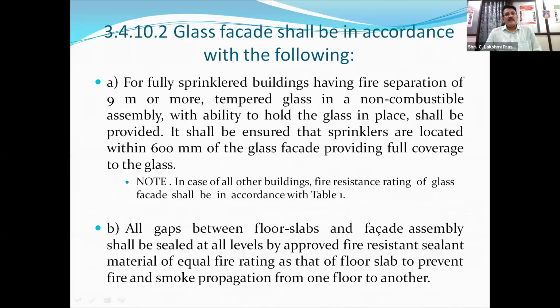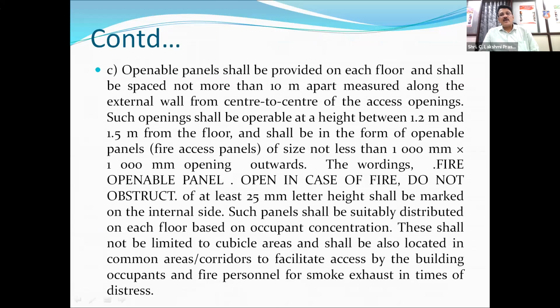NBC has clearly given the fire safety requirements of the facade for a fully sprinklered building having fire separation of 9 meters or more. Tempered glass in a non-combustible assembly, with the ability to hold the glass in place, shall be provided. It shall be ensured that sprinklers are located within 600 millimeters of the glass facade. Then all gaps between floor slab and facade assembly shall be sealed at all levels by approved fire resistant sealant material of equal fire rating as that of the floor slab to prevent fire and smoke propagation from one floor to another. Then openable panels shall be provided on each floor.